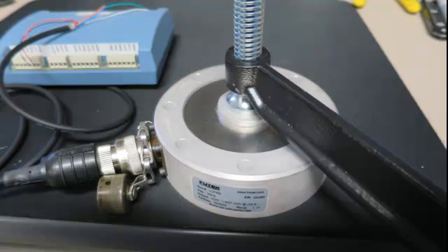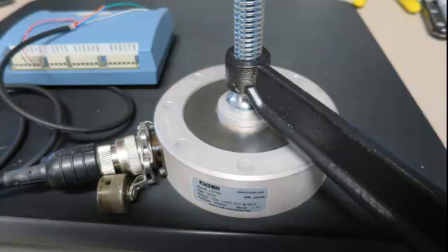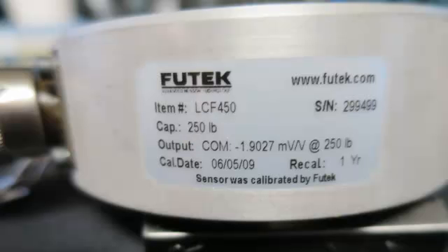The load cell is rated to handle up to 250 pounds and to simulate a load I will use a clamp to squeeze it. For this load cell, the calibration information is listed here and states a maximum weight of 250 pounds and a sensitivity of 1.9027 millivolts per volt of excitation.